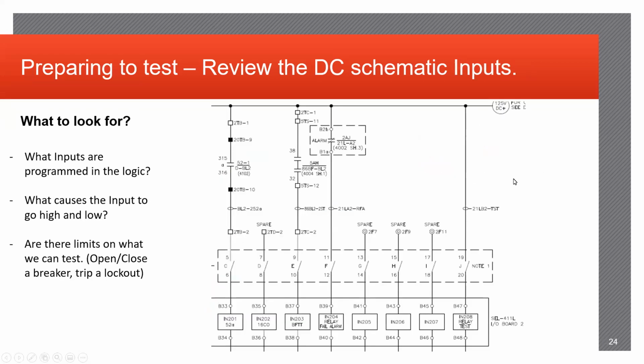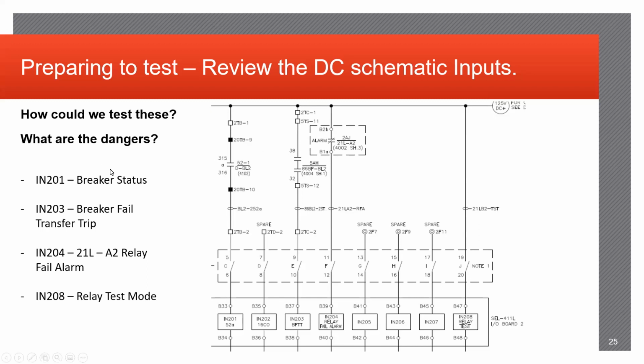So, reviewing DC schematic inputs. On the input side of the relay, you want to identify what inputs are programmed in the logic, what causes the input to go either high or low, and what the limits are, especially with the open and close of a breaker and tripping lockouts. Again, identifying your isolation points, correctly hooking up your inputs on the relay side to your output side of the test set when testing is extremely important.